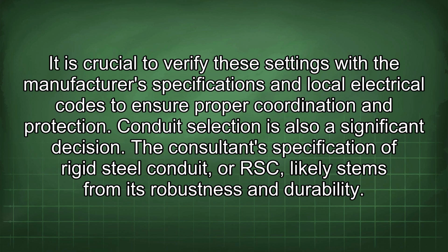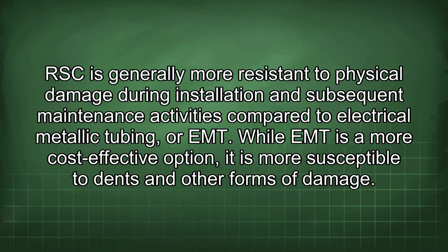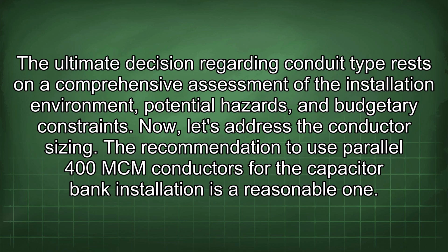The consultant's specification of rigid steel conduit, or RSC, likely stems from its robustness and durability. RSC is generally more resistant to physical damage during installation and subsequent maintenance activities compared to electrical metallic tubing, or EMT. While EMT is a more cost-effective option, it is more susceptible to dents and other forms of damage. The ultimate decision regarding conduit type rests on a comprehensive assessment of the installation environment, potential hazards, and budgetary constraints.